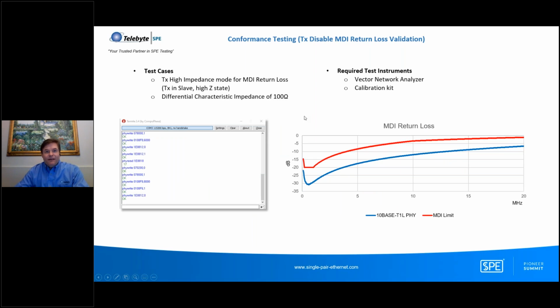The final test we run in the conformance testing is the MDI return loss. This is looking at how close the front end of the device is to 100 ohms. We need a vector network analyzer, and we have to calibrate our cables. We have a return loss limit from the standards here in red, and then we put the device into a high impedance mode and slave mode, so the transmitter is disabled. Then we look at the characteristic impedance using S11 parameters from the vector network analyzer. We see here that this device at 10BASE-T1L is passing the return loss. So it's a very good 100 ohm characteristic on this device. This is important for error-free data transmission. You want to match the impedance as closely as possible.